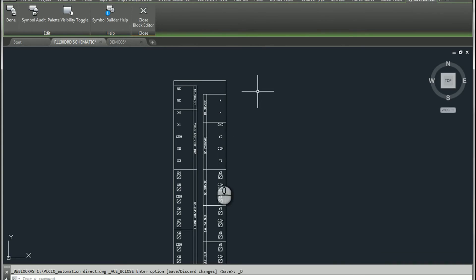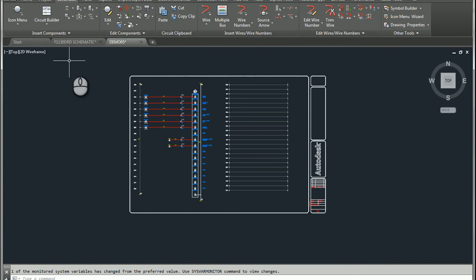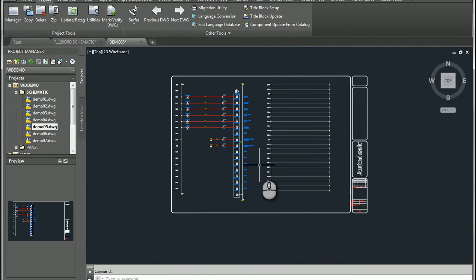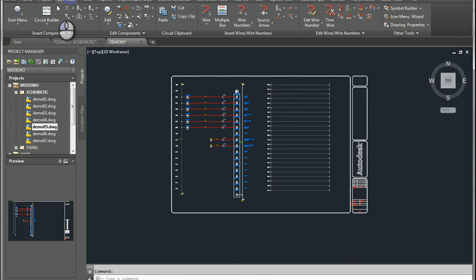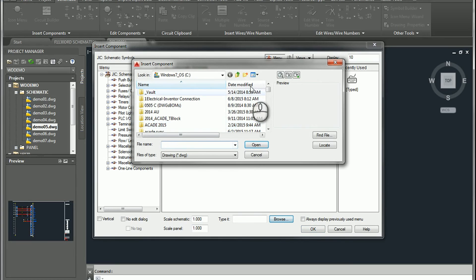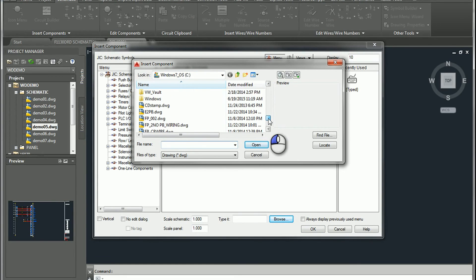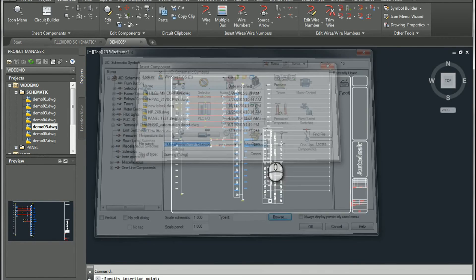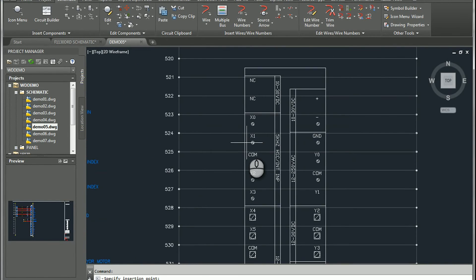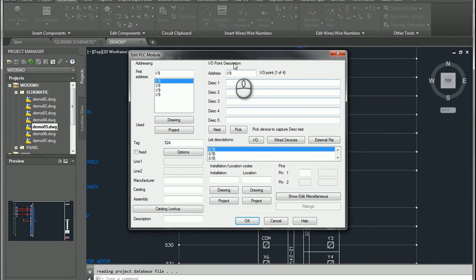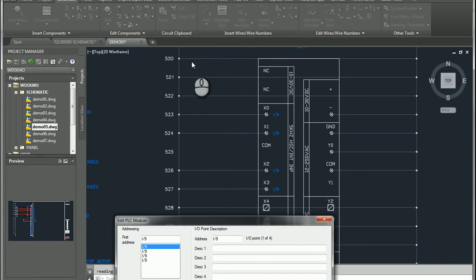I'll choose No to insert it for now. Going over to my demo — if your project manager tab isn't up, go to Project to turn it back on. I'll go to my icon menu, and since the symbol isn't on there yet, I'll choose Browse, navigate to my C drive, and open the PLC IO file I just created. It comes in just as expected. If I'm good at placing it, it will trim the wires for me automatically — and it does. If that makes sense for your power scheme, great; if not, you'll need to clean those up anyway.